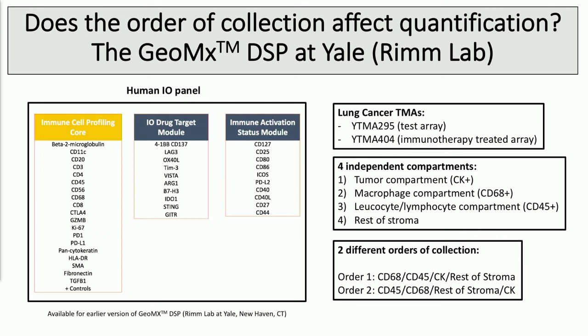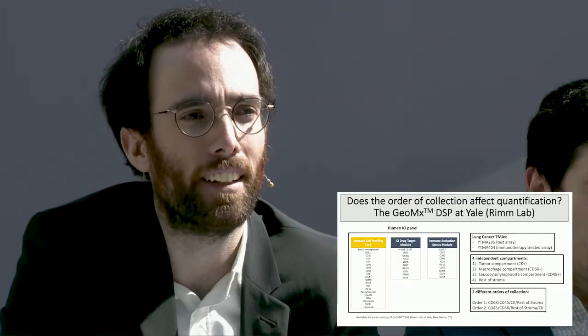The very first thing we did when we got the instrument at Yale was to perform on-site validation of the technology. We tested whether the order of collection of different compartments could affect quantification. If the compartmentalization process is not very accurate, or if the laser resolution is not very accurate, there is a risk of bleed-over in quantification between compartments in close proximity — this would lead to over-representation of targets collected first versus last. So we took two serial sections and tested two different collection orders: CD68, CD45, CK, rest of stroma versus CD45, CD68, rest of stroma, CK, then compared quantification between the two orders.